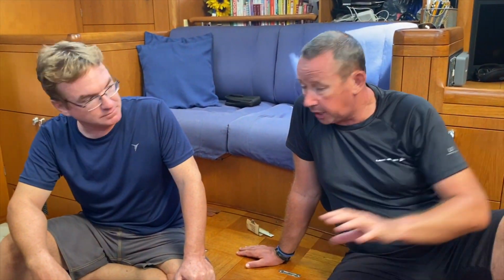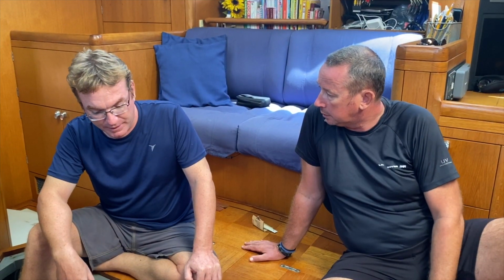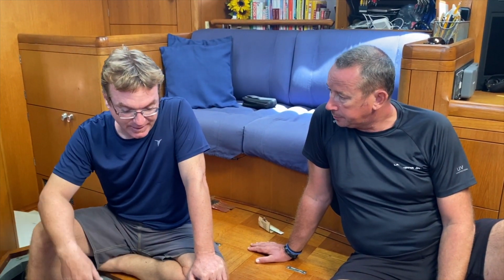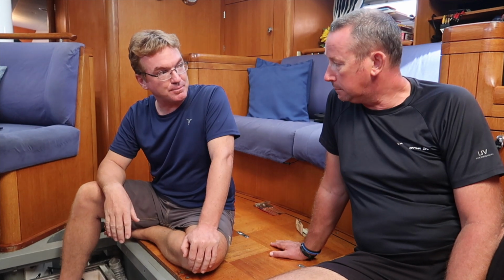The system on Briticon is working and reading right. So what happens if there's a big discrepancy between what the batteries say and what your monitor says? Why is that? Good question. I see it often, and it's almost always due to corrosion here or there or somewhere else, and we'll talk more about that in a minute.